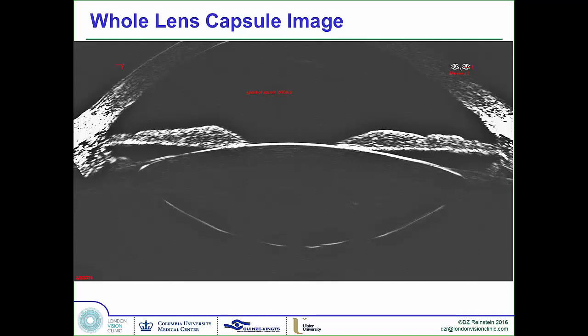We can scan the whole lens capsule — this is a world first. This is a device that can scan in six degrees of freedom and therefore can capture all of the angles of the capsule. It means that finally, where we're operating, we can actually see behind this dark side of the moon — we can actually now know what we're doing and where we're doing it.